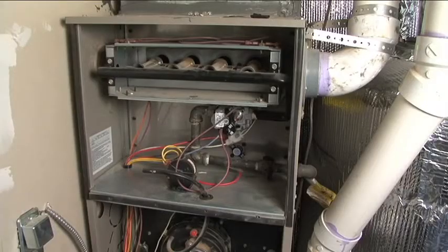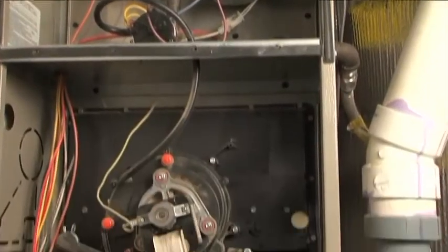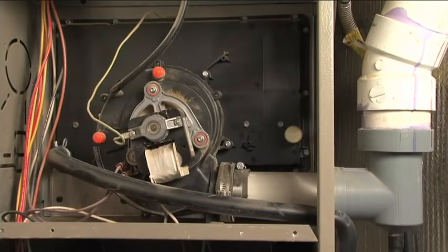First, we put the burners high and use our draft-inducing fan to pull those combustion gases down through our heat exchanger. So as the gases naturally want to rise, we pull them back down, making those combustion gases spend more time in the heat exchanger.